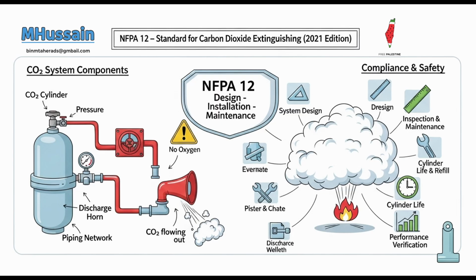Additionally, the oil content must not exceed 10 parts per million by weight. Very low oil content. Why so strict? These aren't just arbitrary numbers, they are critical. Impurities, such as excess water or oil, could significantly hinder the system's performance. Water could lead to corrosion within the piping, especially given the cryogenic temperatures, and oil could leave undesirable residues or even act as a fuel source itself. Makes sense. Don't want corrosion or more fuel. Exactly. Maintaining this high purity ensures the agent remains effective and non-damaging. For this reason, the standard strongly recommends periodic analysis of the CO2 supply to ensure it consistently meets these strict quality benchmarks throughout its service life. So regular testing of the gas itself. Yes, to ensure it stays pure.